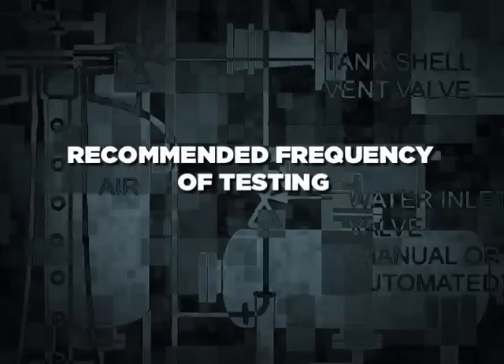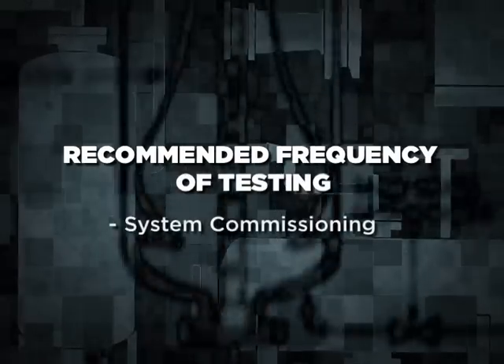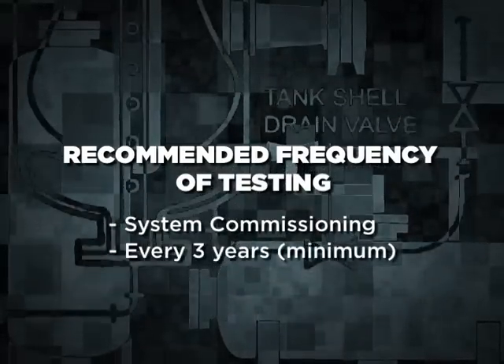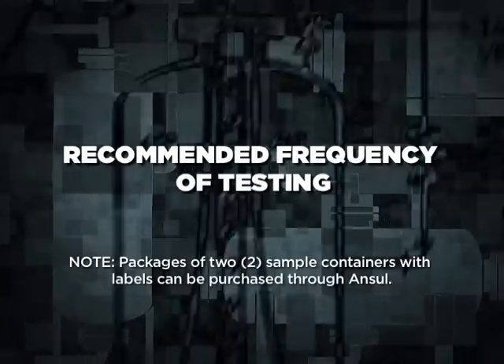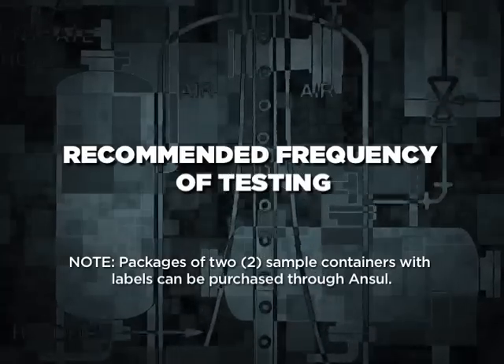In addition to annual testing, Ansul recommends that proportioning tests be done at system commissioning and every three years minimum thereafter. Ansul also recommends that standard quality analysis testing be done annually by the Ansul Agents Laboratory. Our Agents Lab not only tests the chemical properties of the sample, but also does lab-scale fire testing to ensure the product's performance.